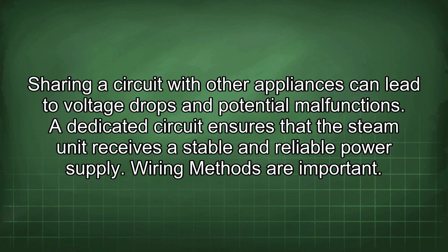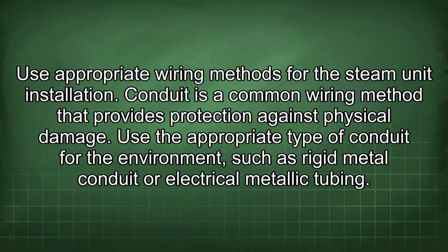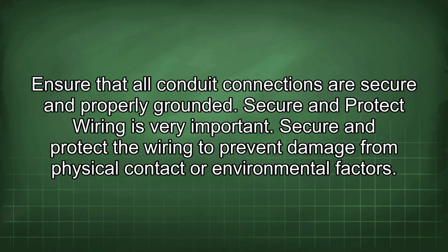Wiring methods are important. Use appropriate wiring methods for the steam unit installation. Conduit is a common wiring method that provides protection against physical damage. Use the appropriate type of conduit for the environment, such as rigid metal conduit or electrical metallic tubing. Ensure that all conduit connections are secure and properly grounded.